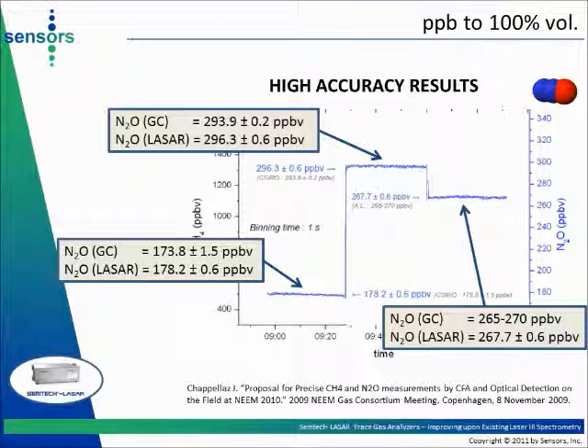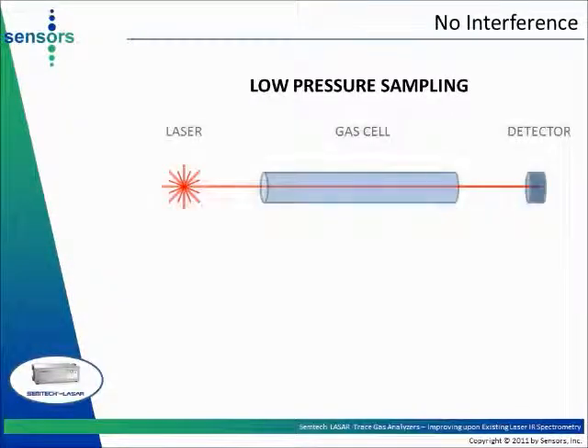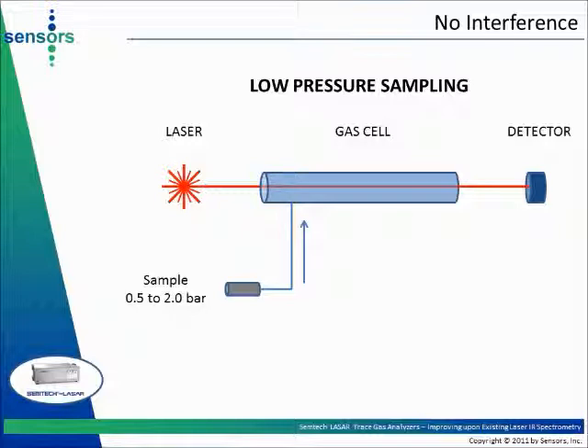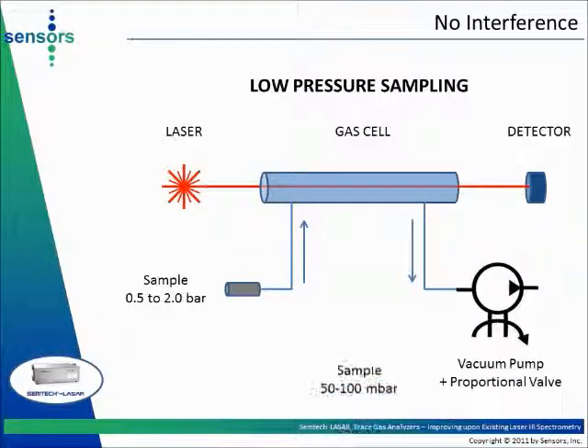Signal integration time was only one second in this experiment. The Semtech LASAR relies on low-pressure sampling and very high-resolution spectroscopy to minimize interferences in the measurement. In its standard configuration, the Semtech LASAR accepts gas sample pressures at the sample intake point ranging from 0.5 to 2.0 bars. A vacuum pump draws the gas sample through a critical orifice, lowering the pressure inside the entire gas flow sampling assembly to typical values of 50 to 100 millibar. A proportional valve enables pressure regulation at 0.1 millibar throughout the sample system.